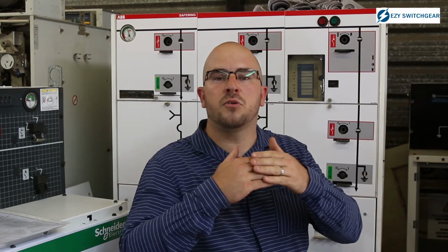The last test is the ductor test. The ductor test ensures that internally in your switchgear, there are no loose connections. So a ductor test will pick up a loose connection quite quickly and make sure that you don't have any hot connections in your system. When doing these tests with proper test equipment, you ensure that the unit will not fail in the foreseeable future.